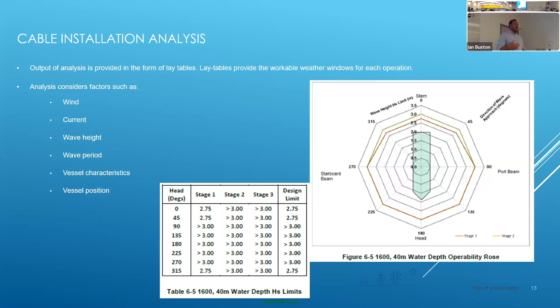So there's pros and cons for different vessel designs, and that's why we run the analysis based on particular vessel characteristics. You get a set of characteristics for each vessel supplied by the naval architect who designs it, and they also do small scale testing to get these sets of parameters, which feed into the Orcaflex analysis and then into the installation conditions allowed during cable installation.